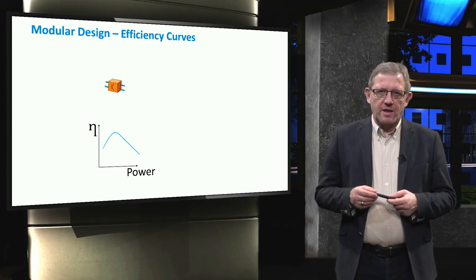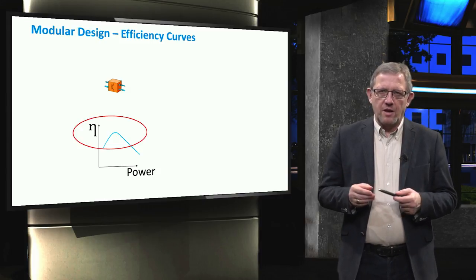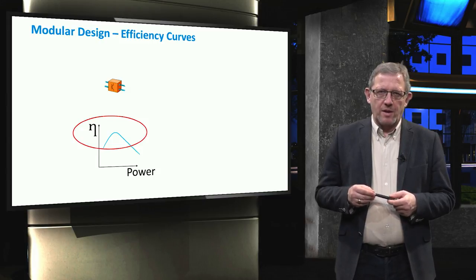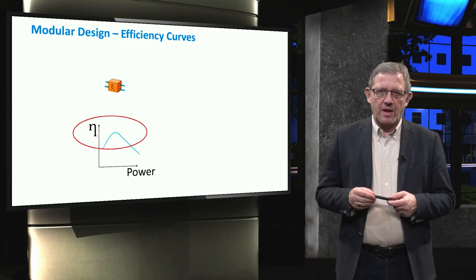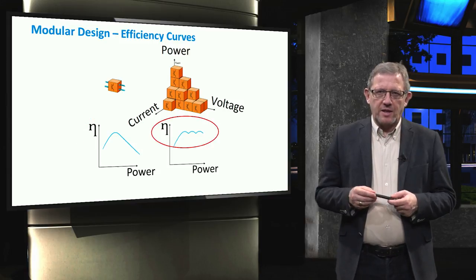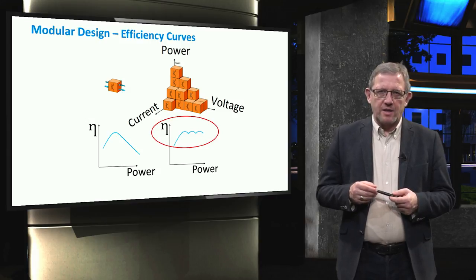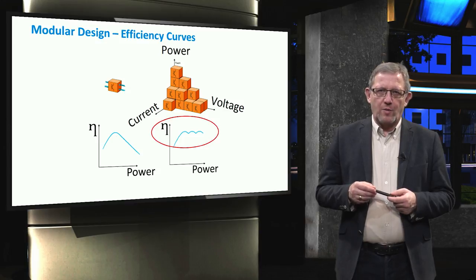It is worth mentioning that the modular design of DC converters will result in a higher efficiency. The efficiency curve of one single power converter is shown, just for illustration, where the overall efficiency highly depends on the operating point of the transformer. Typically, the transformer has the maximum efficiency around 98-99% of the nominal power. If the design is made in a modular way, it is possible to operate these modules in such a way that the efficiencies remain high for a wide range of operating conditions.